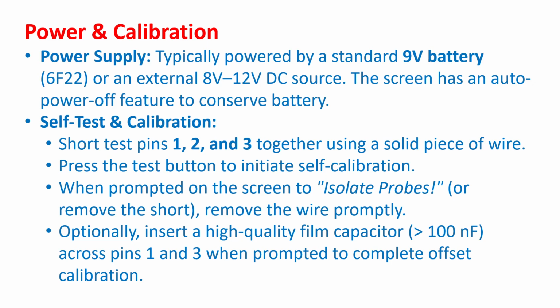Self-test and calibration: short pins 1, 2 and 3 together using a solid piece of wire, then press the test button to initiate self-calibration. When prompted on the screen to isolate probes or remove the short, remove the wire promptly. Optionally, insert a high quality film capacitor of more than 100 nanofarad across pins 1 and 3 when prompted to complete offset calibration.